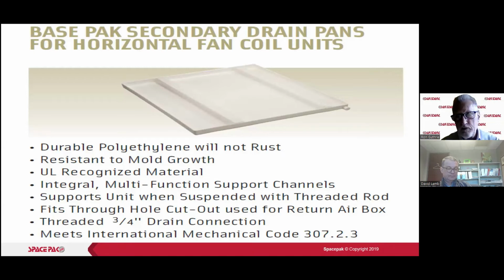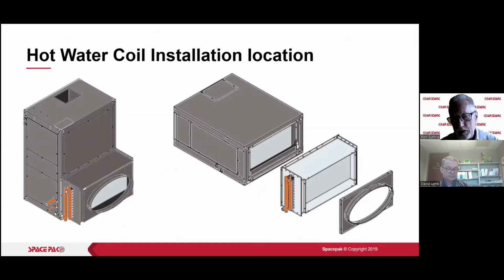Just remember, though, I think it's about 0.11 or 0.12 pressure drop on these coils. Remember that we only have 0.25 pressure drop to deal with on the return end. All right, so that means we're never going to put any pleated filters on our units, unless you have a lot of room as far as pressure drop goes. I've seen pleated filters at 0.36 by themselves. So where we take it out and we reduce the pressure by 0.36, it's crazy. No super filters that stop everything, including the air. Don't use anything like that.